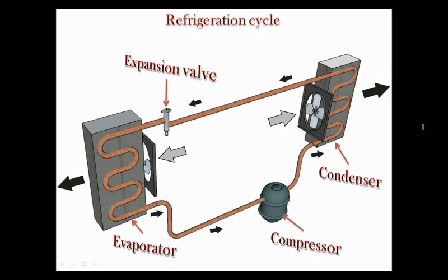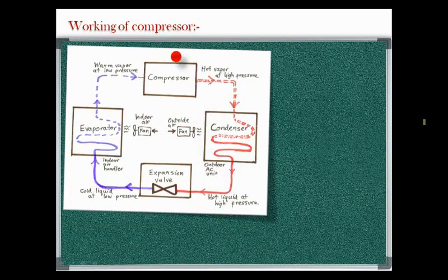We will begin our discussion with the compressor. The compressor is also known as the heart of a refrigeration system. It keeps the refrigerant flowing through the system at a specific rate of flow and at a specific pressure. The compressor, located between the evaporator and condenser, has two important lines: a suction line that is a low pressure line, and a discharge line which is a high pressure line.